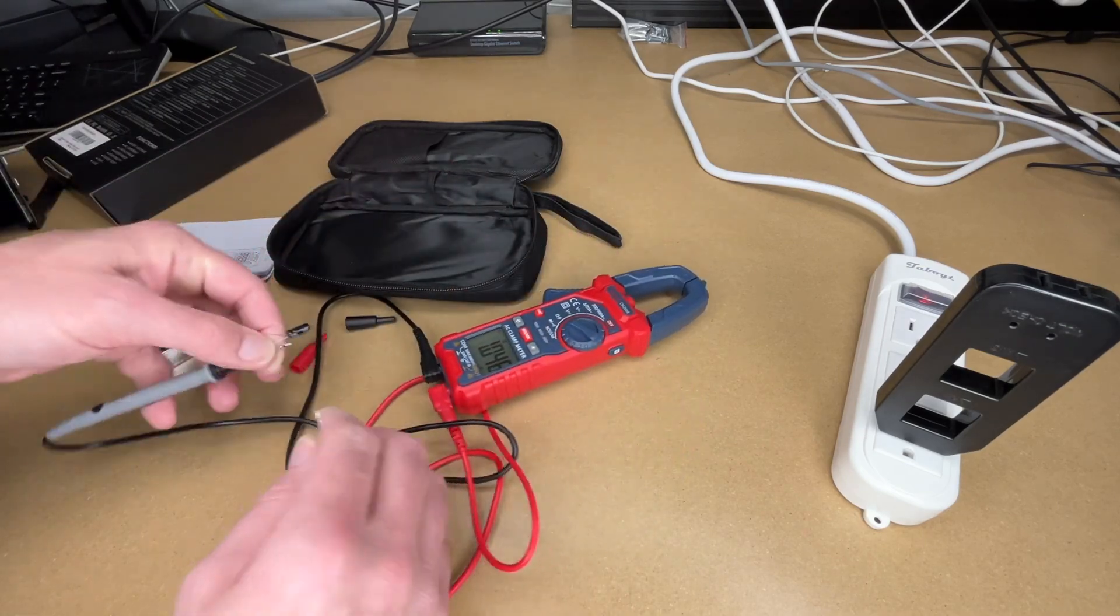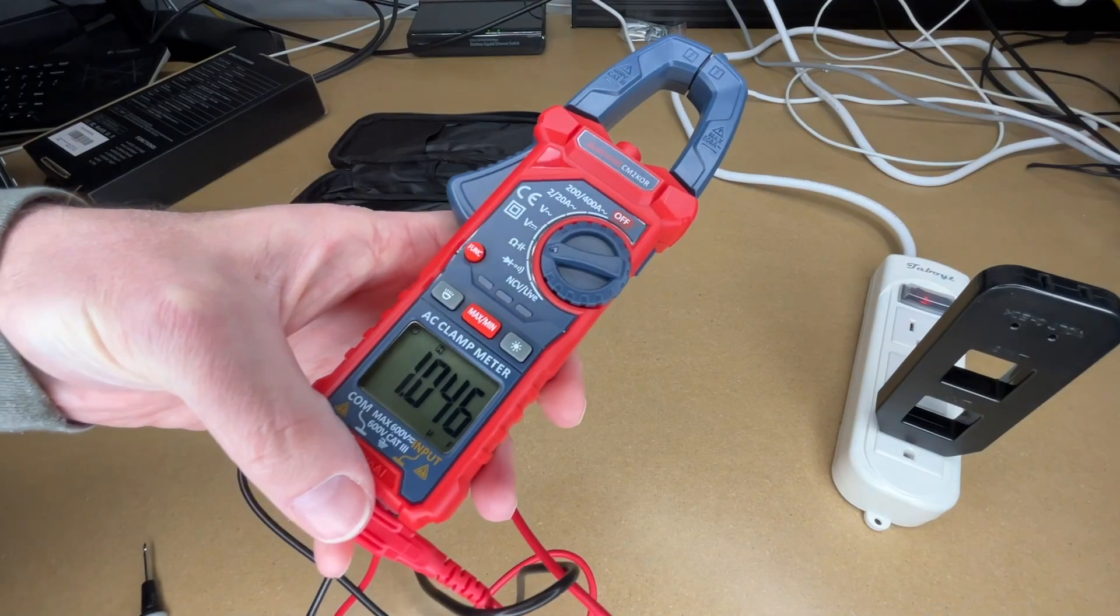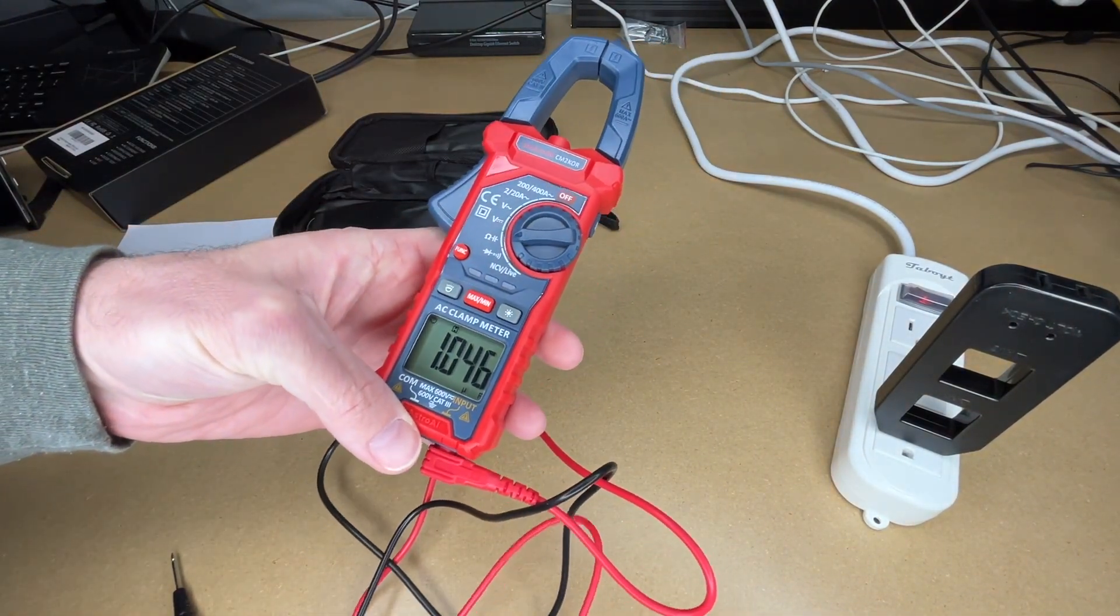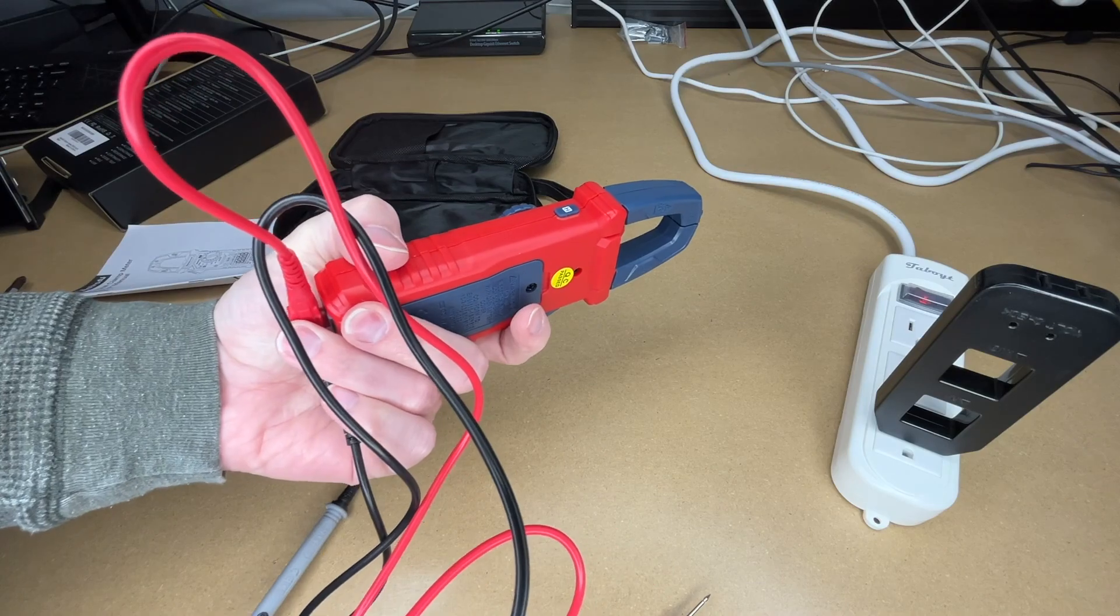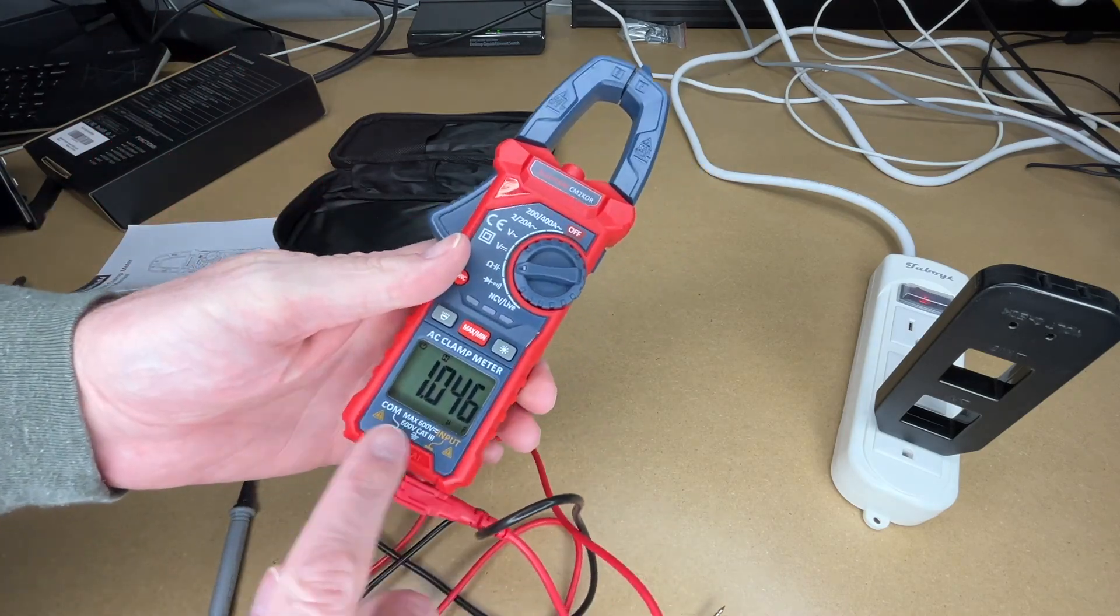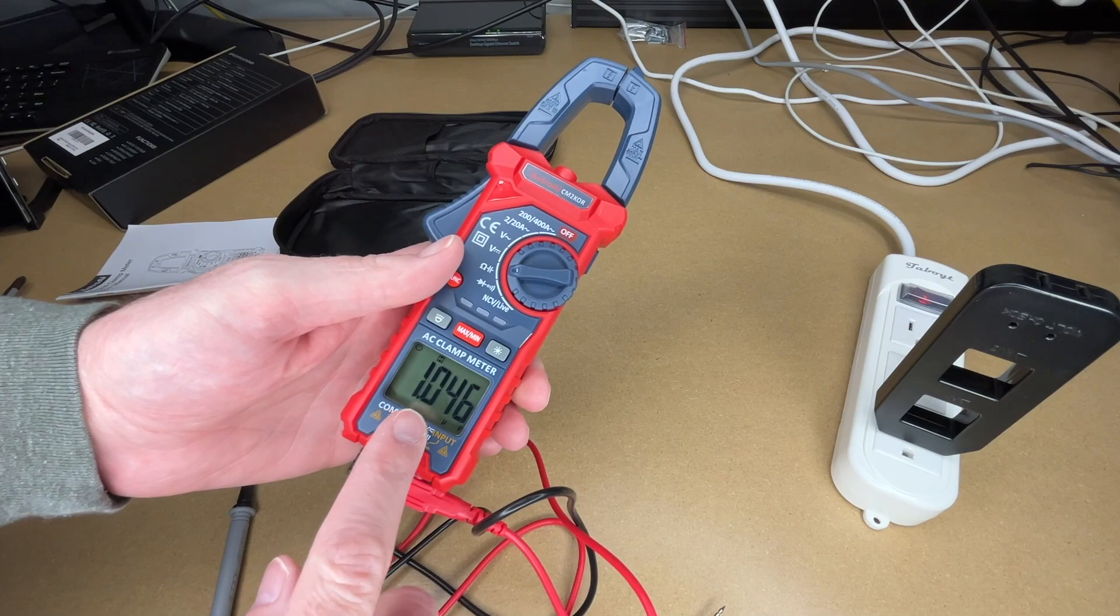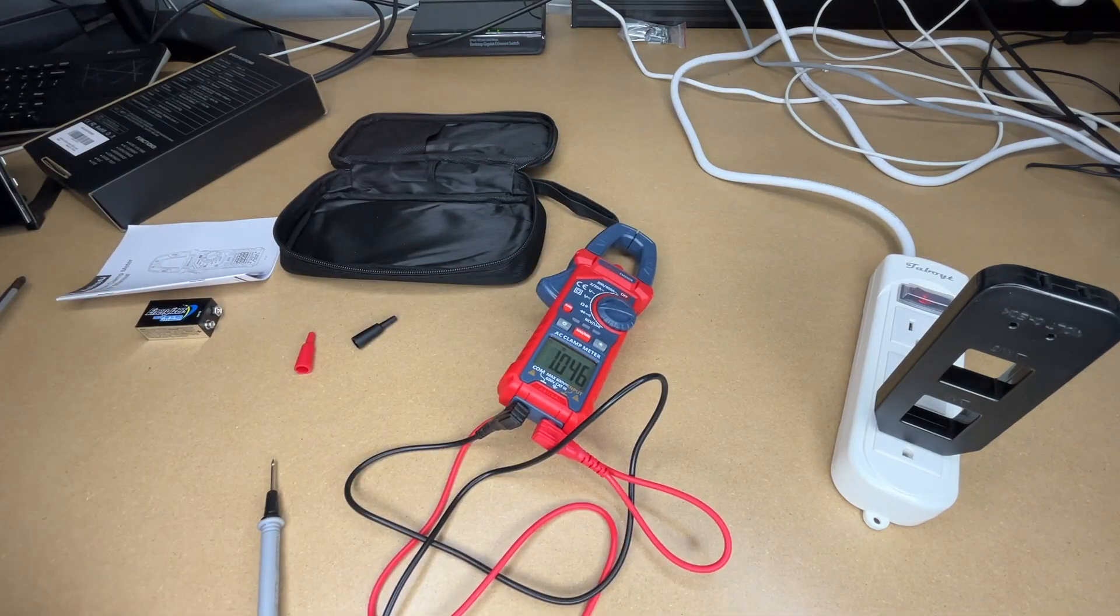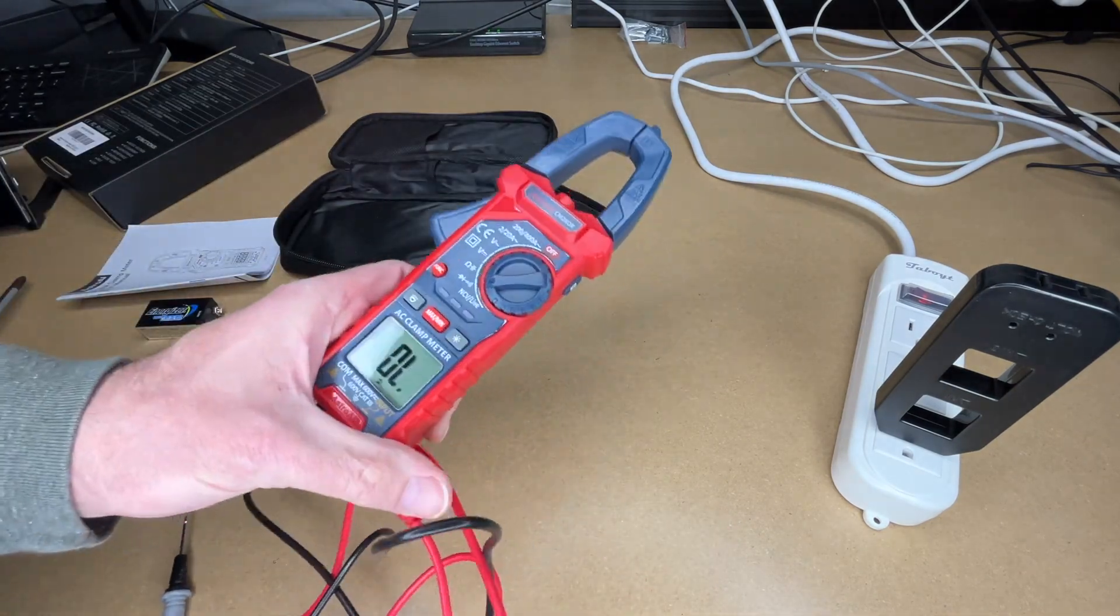I'll hit hold on the side, so I press the hold on the side there, so now it will retain this value so it's easier to read. So if you're measuring something you can't read, like the meter's in a weird position when you're measuring it, you can press that hold and then it will store that value. So we have 1.046 microfarad, so that's within tolerance, that's what you would expect.